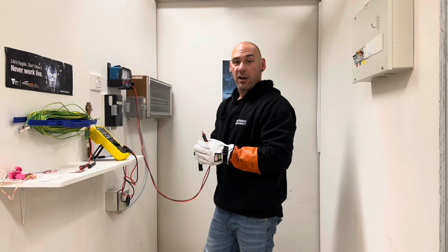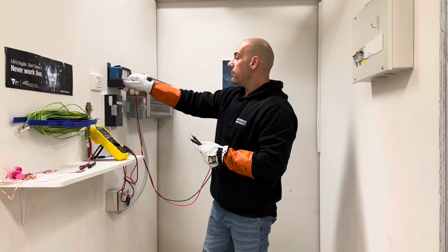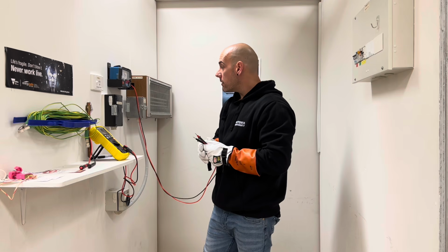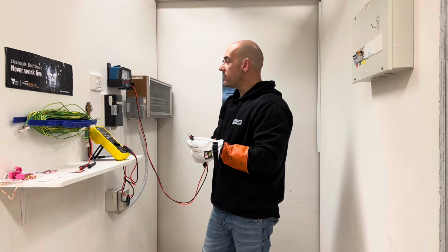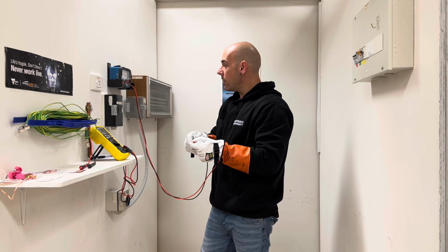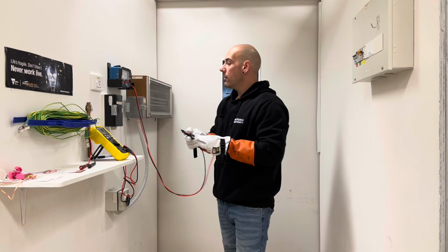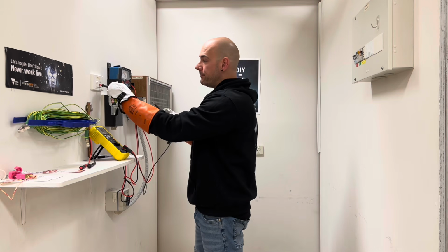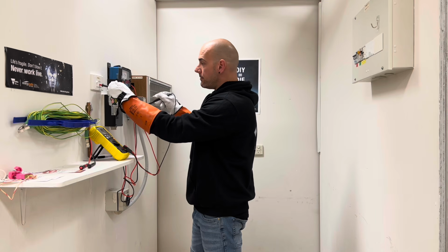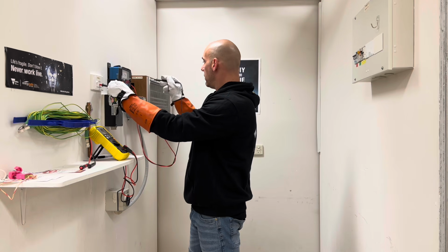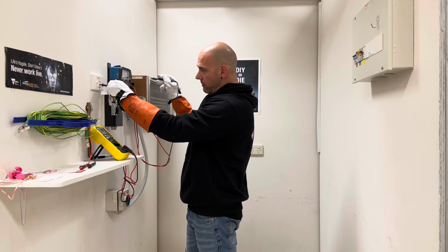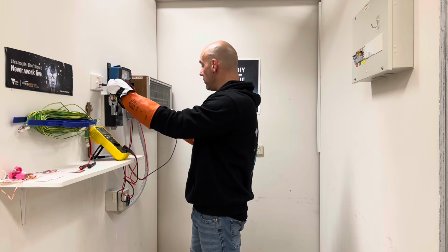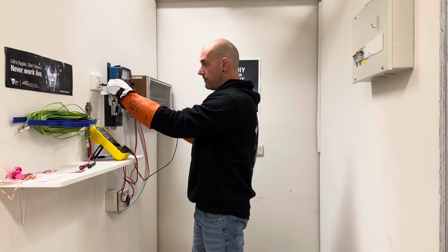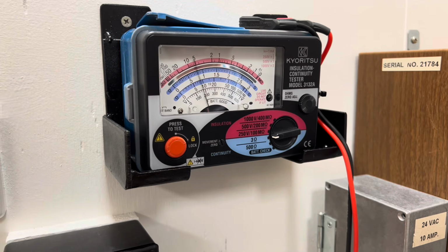Now we're going to do a continuity test of the earthing system. First, we check our battery. Okay, that's working. Great. 3 ohm scale, short our leads out, and 0 our meter if needed. We go from the reference earth to the appliance frame, at least 3 spots, and we're getting a reading of 0.1 of an ohm, which is under the required 0.5 of an ohm, which is a good earth. And just make sure our meter's working. Okay, great. I'm quite happy with that earth.